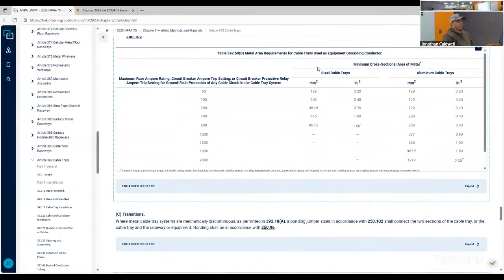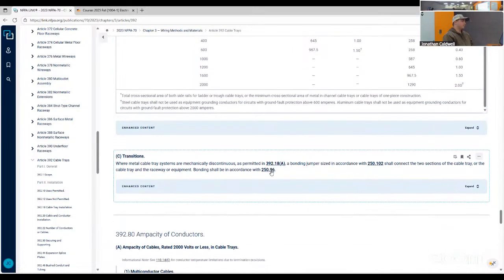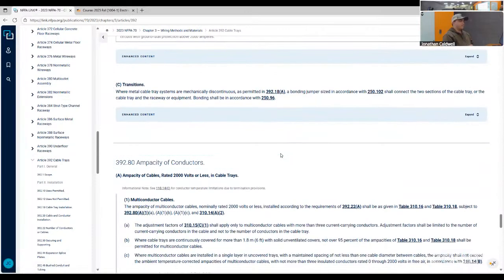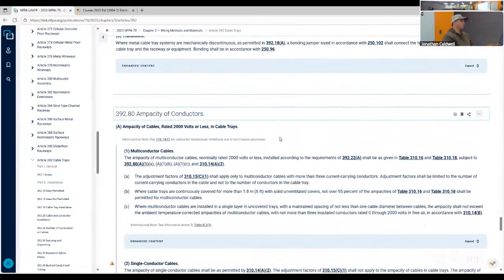Like I said previously though, most people will deal with basket tray. Make sure you're using the UL listed fittings and the manufacturer recommended fittings with that grounding. It's not like the manufacturer has a 100% markup on their fittings and things like that. No, they're actually relatively priced and they make sense. So just use them.